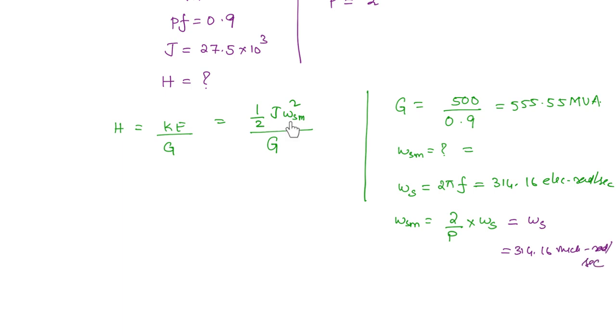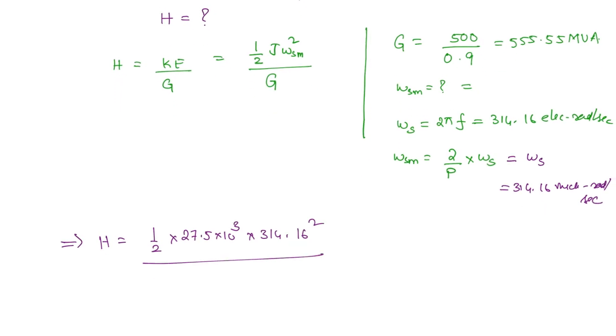Now we know J, ω_SM, and G, so we substitute all values: H = ½ × 27.5 × 10³ × (314.16)² divided by 555.55 × 10⁶. This gives H = 2.44 seconds.